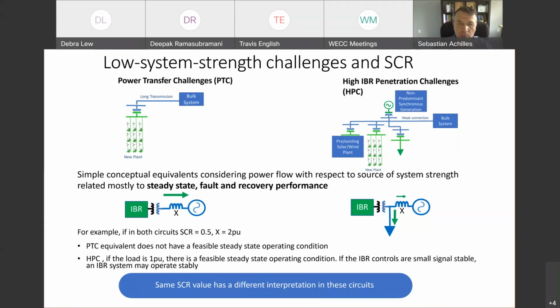So these two systems, it's good to think of an example. If we assume that both of these circuits will have a short circuit ratio of 0.5, that's a very low number compared to the things that we're typically discussing in the industry. So the short circuit ratio is 0.5. The reactance will be 2 per unit in the base of the inverter-based resource megawatt rating, for example. If we define a system like that, the reactance in both systems will be 2 per unit.